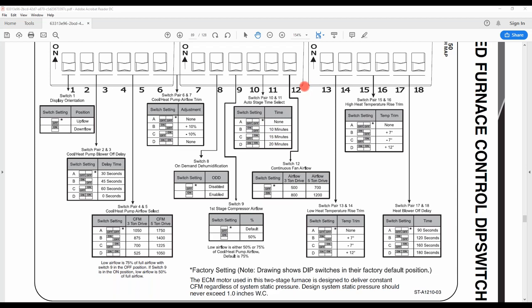Moving to dip switch number 12. So here's our continuous fan airflow. It comes at the lowest setting from the factory, which is off position. A 3-ton drive is 500 CFM, and 800 CFM if you flip it to on. A 5-ton drive, you have the option of 700 or 1200 CFM. Notice you only have 2 options here when using the dip switches and not using the Econet thermostat.